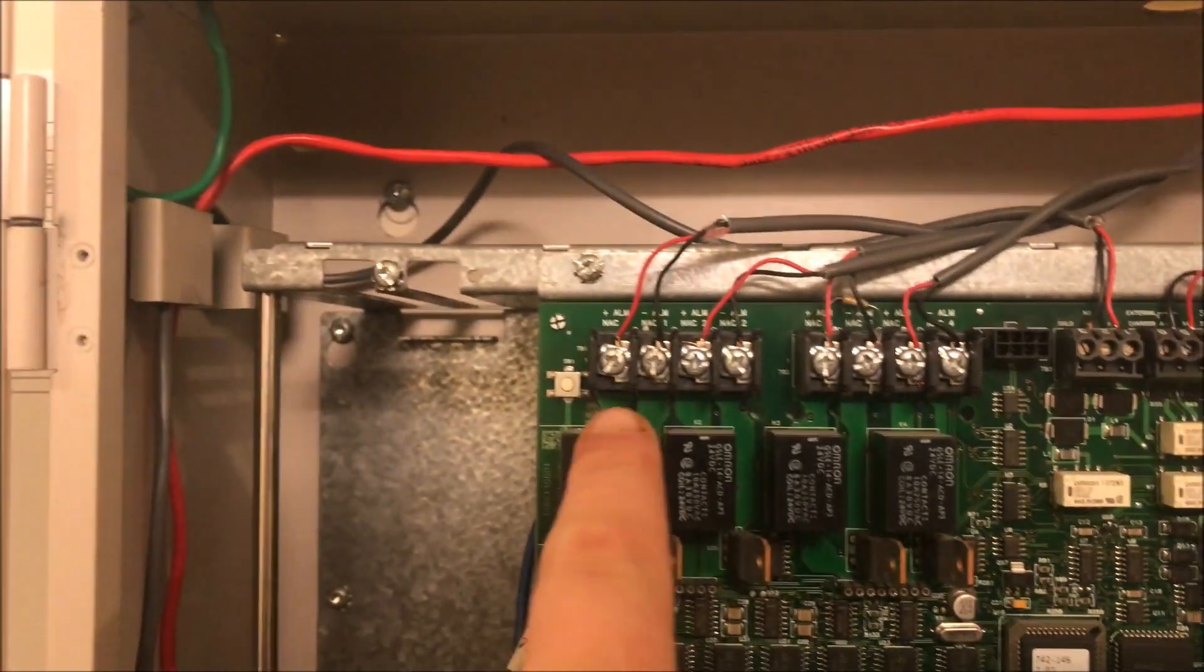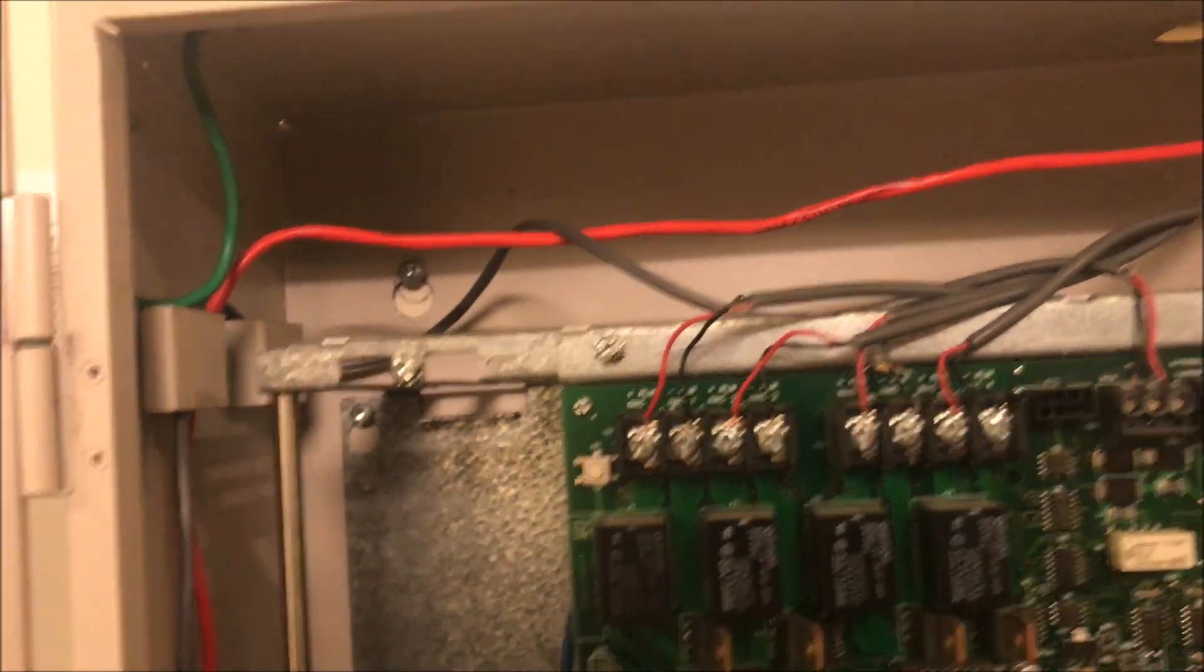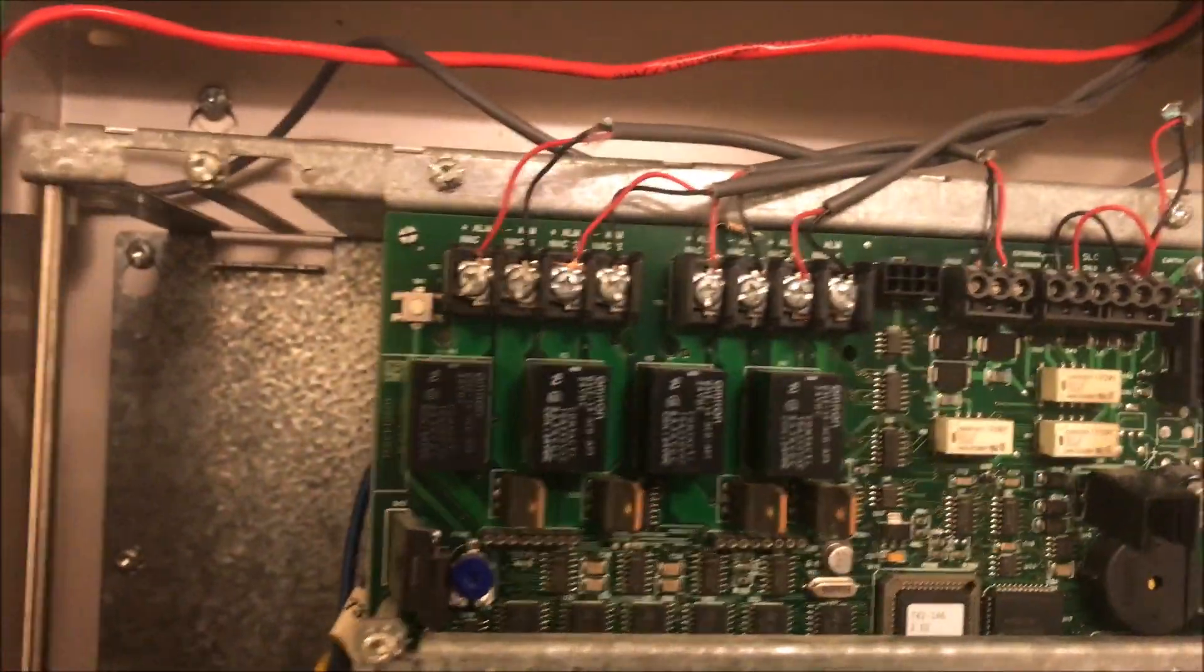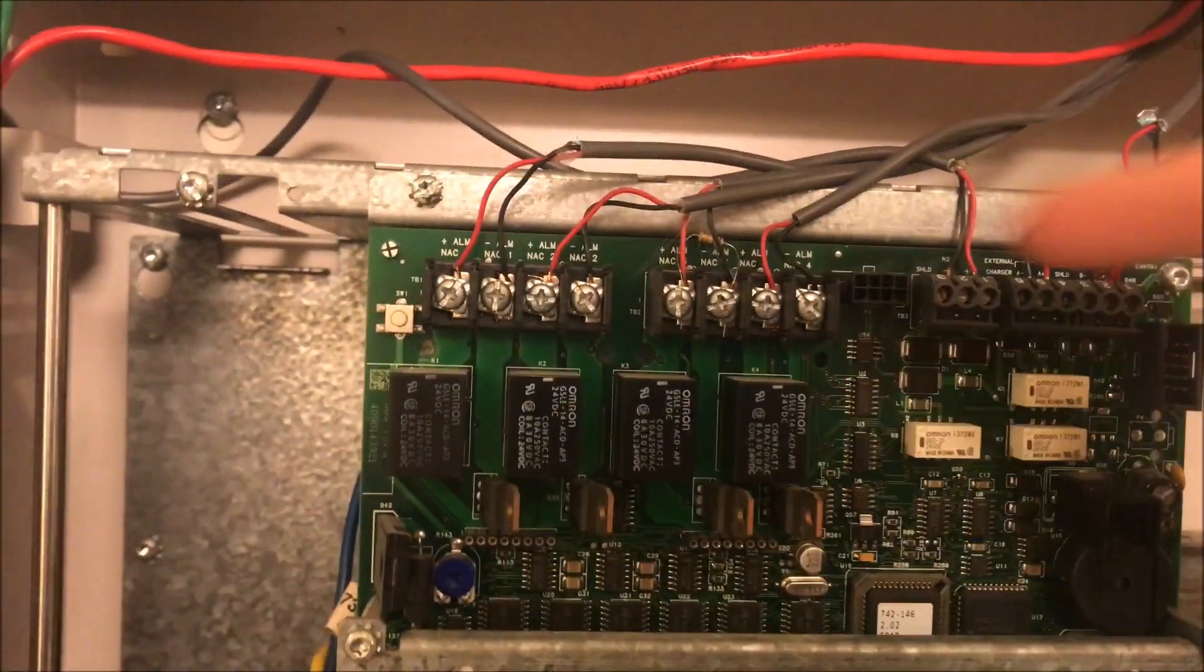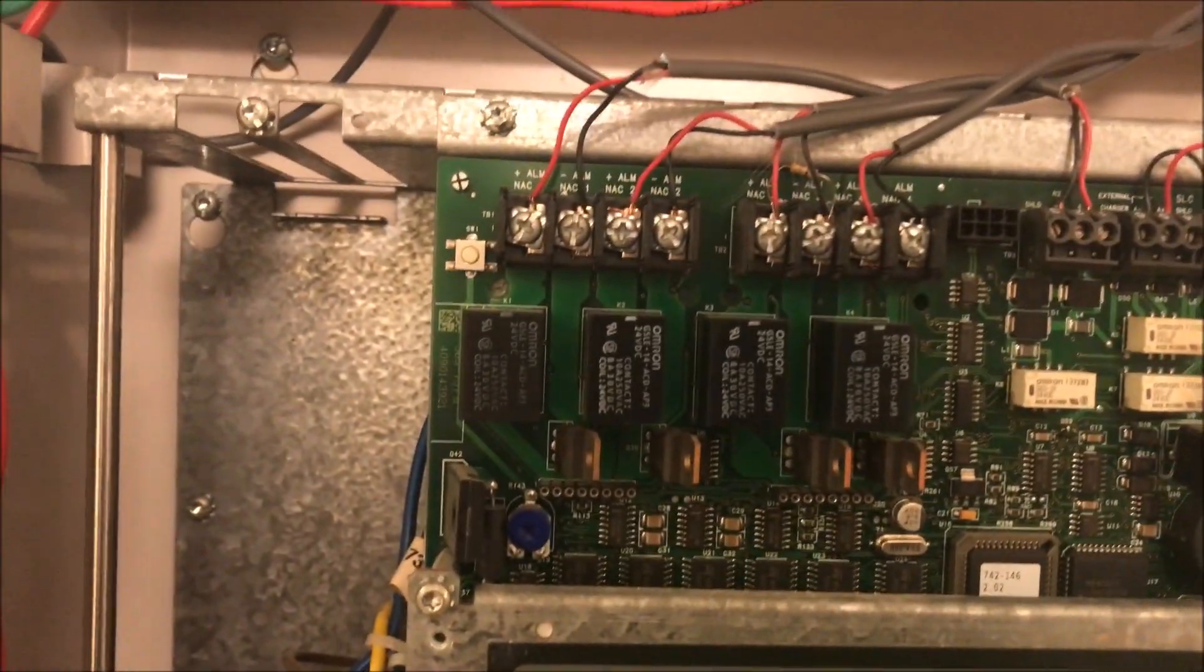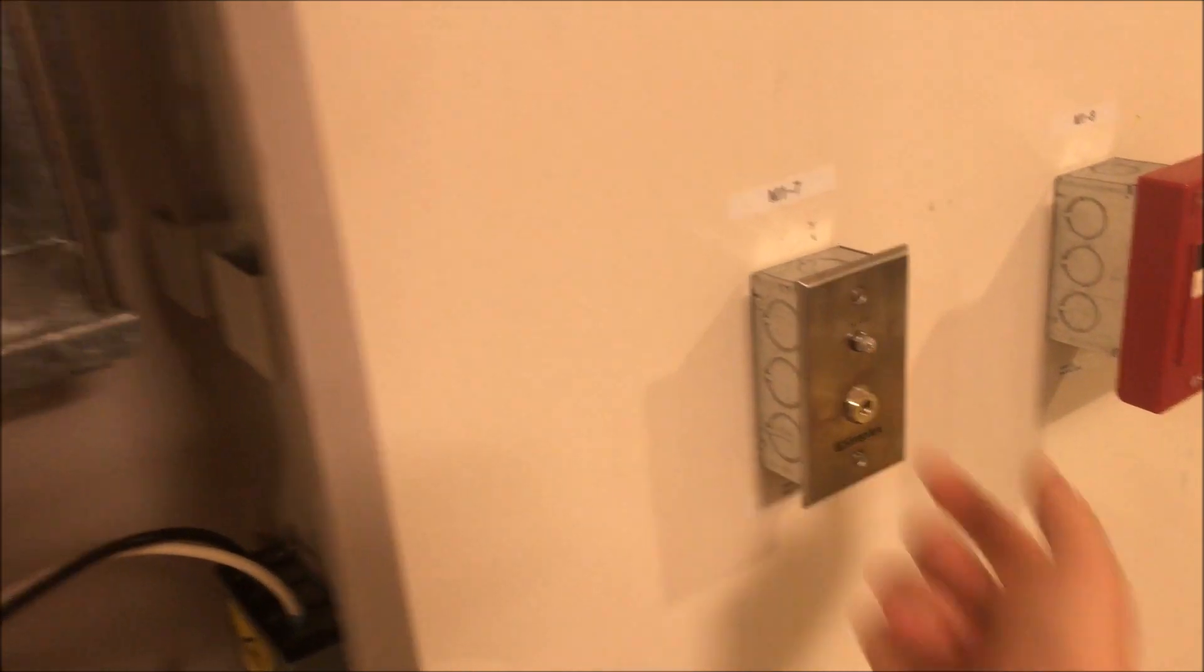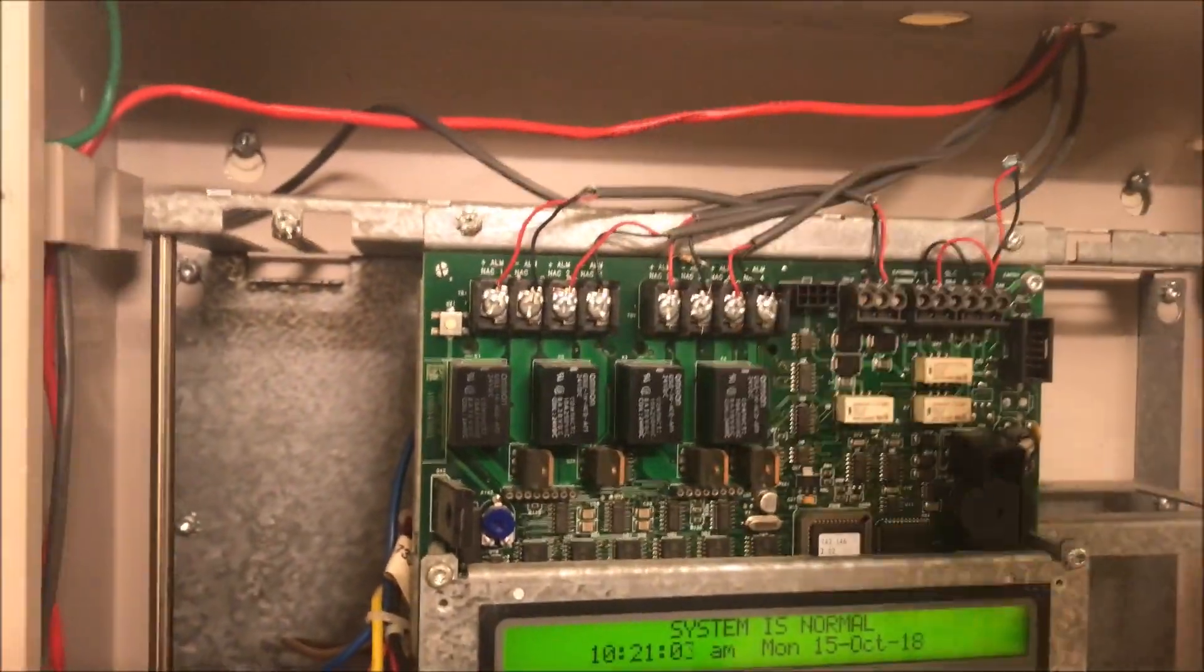Starting at this top row, these are your NAC zones—NAC 1, NAC 2, NAC 3, NAC 4. Those are simple Class B wiring with an end-of-line resistor. On a Simplex 4010, it takes a 4.7 kilohm resistor at the end. You can see one there. I have the end-of-line resistor because I need supervision, but NAC 3 is just the LEDs for my key switches. That's all your NACs, and on the other side you can see my whole rat's nest of wiring.